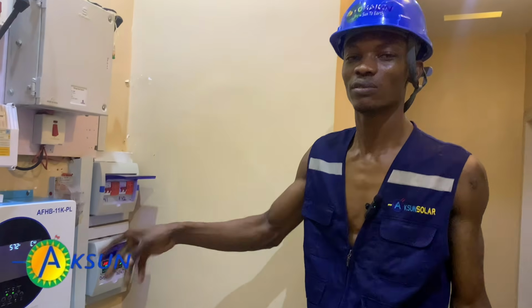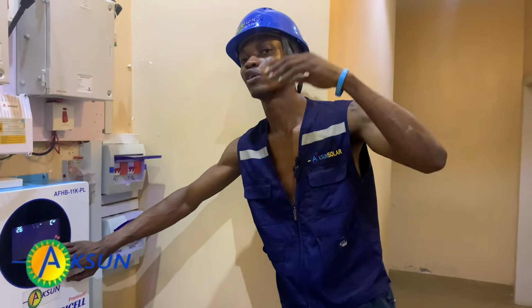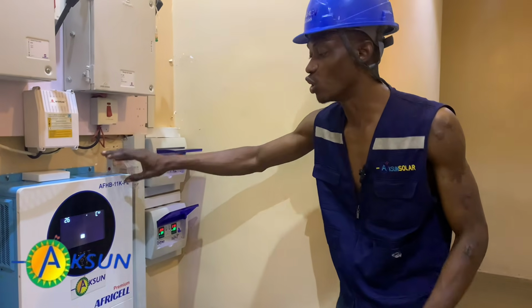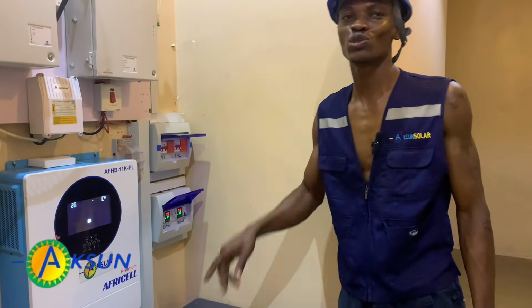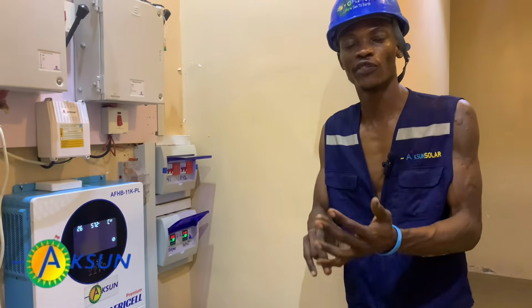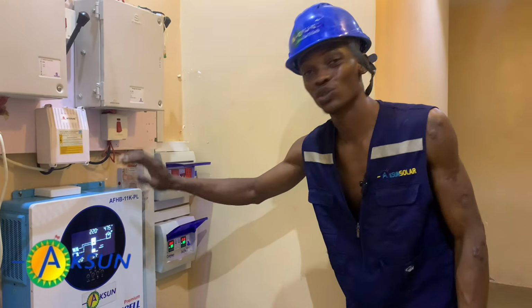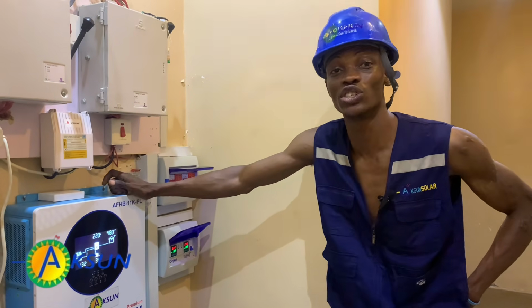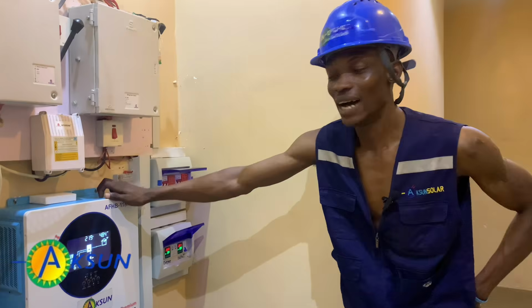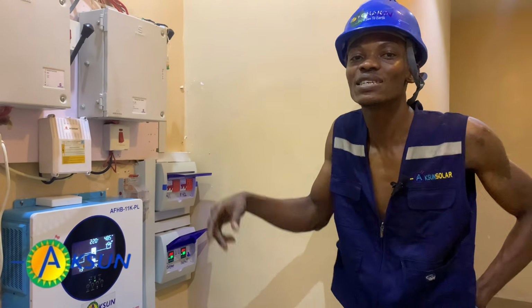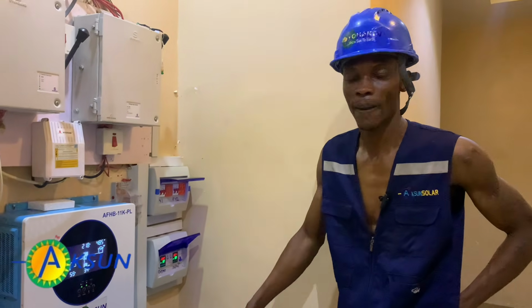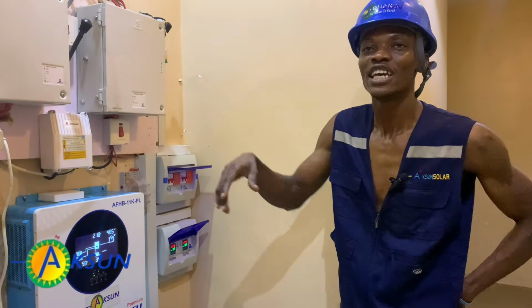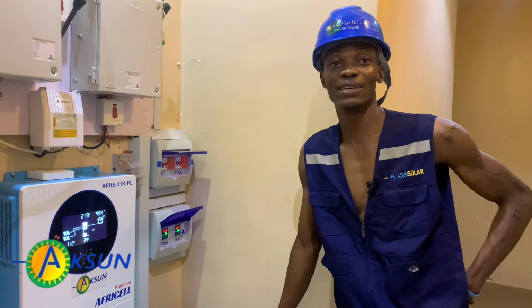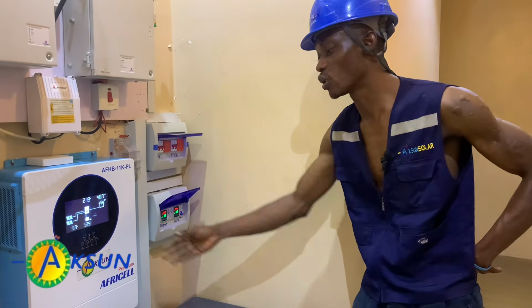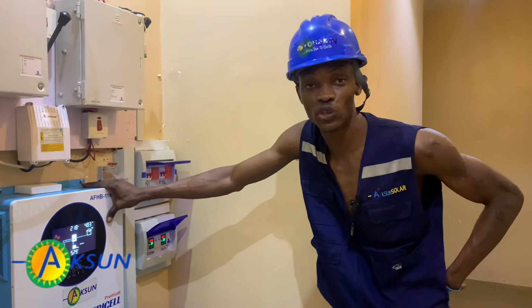Most installers make this mistake very often. I've come across a couple of videos where some installers think that because your inverter and battery communicate, you don't need to do your settings for bulk voltage, float voltage, and cut-off voltage. It is very, very important that you do these settings. Just because they still communicate doesn't mean you shouldn't set these. The people who designed this inverter put that option there because they want you to do it, so that in case these two fail to talk to each other, it's that setting that will be used. It also helps your battery not enter sleep mode whenever it's low, so that the client doesn't have to call you to come and wake up the battery, especially for systems that don't even have a wake-up function for the inverter. You get it now?